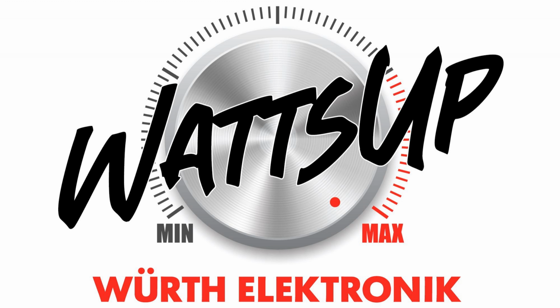In regular operation, when you have these two Y caps and the X capacitor, you have to take care about the leakage of these capacitors, because according to the norm, you have to pay attention that the current on the PE doesn't trip your fuse. You sometimes have a safety fuse, and you cannot put too big values here.